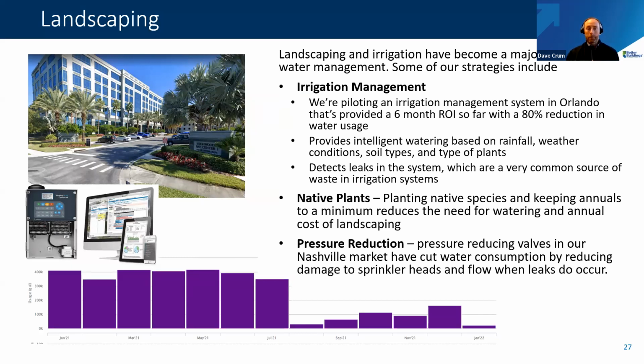So huge help there. And last thing for us, we actually did have a situation in one of our Nashville buildings where the building was located pretty close to the water tower and had really high water pressure, and it was actually blowing the heads off of the sprinkler system. So they put a pressure reducing valve in there.